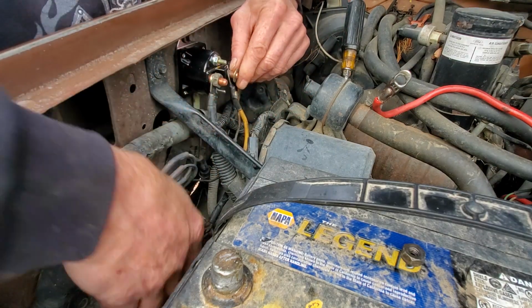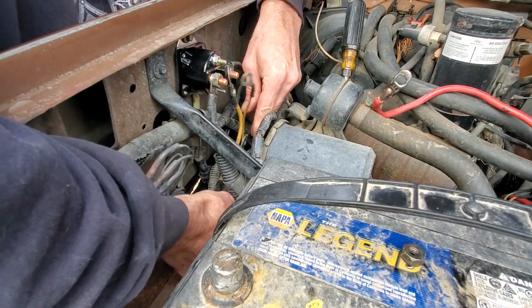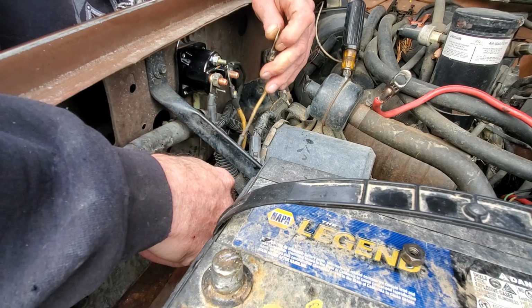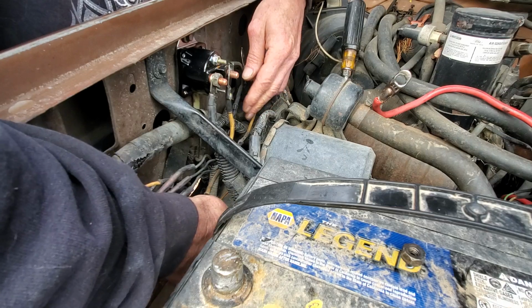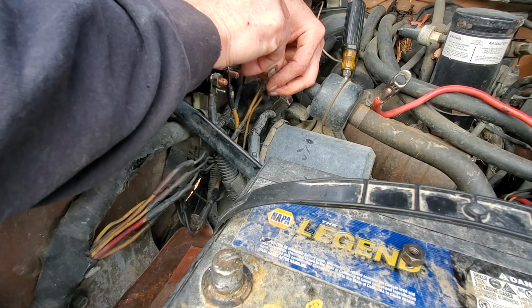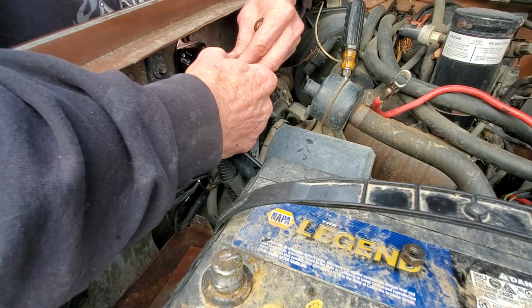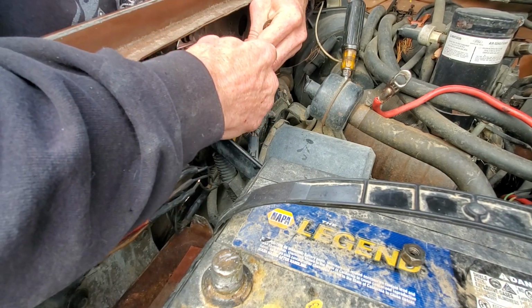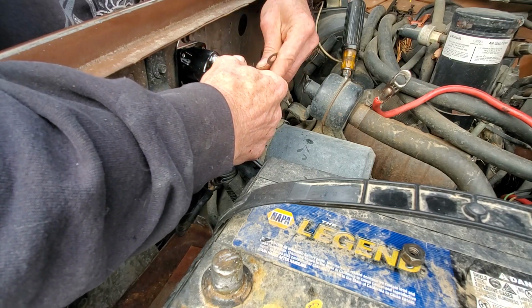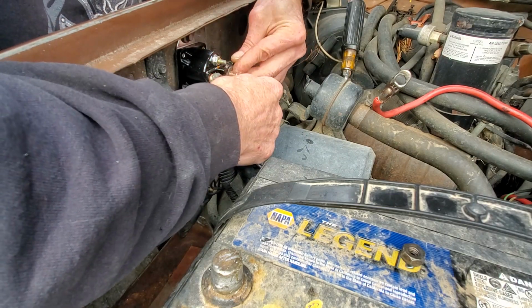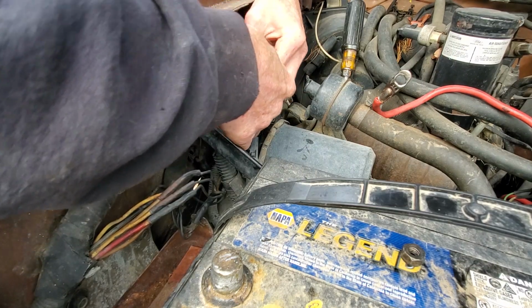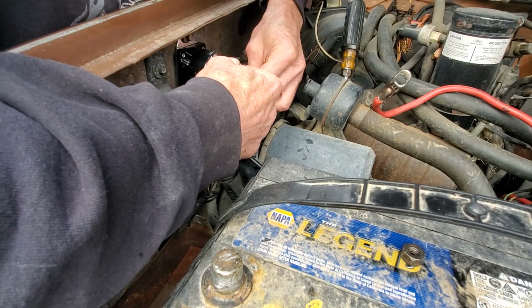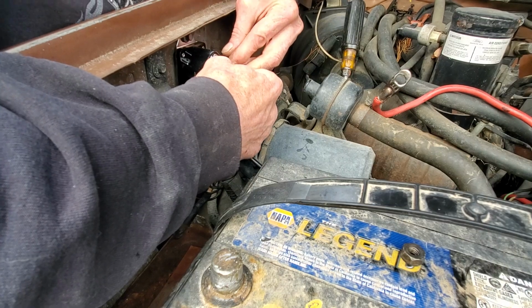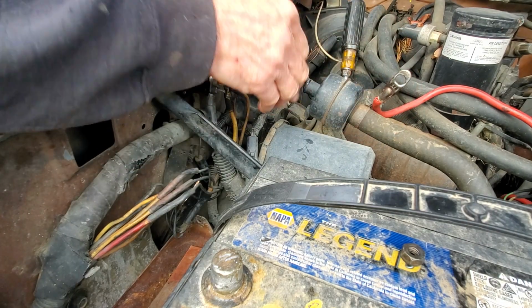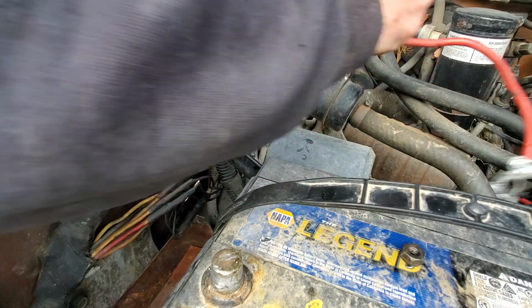All right, so here we go — there's that fuse link. Fuse links give you wiggle room to allow for those volatile scenarios where you're not having a constant, predictable amp draw all the time. Now, in the world of circuit breakers, those are more calibrated — they'll trip at a certain amount of time, at a certain amperage demand. Fuses will blow open, but they're not necessarily calibrated to blow at the same fault current or fault condition every time. Then you have fuse links, which have a wide bandwidth of what it takes before they really blow wide open.